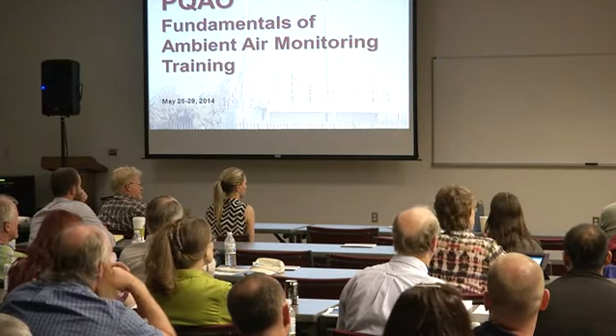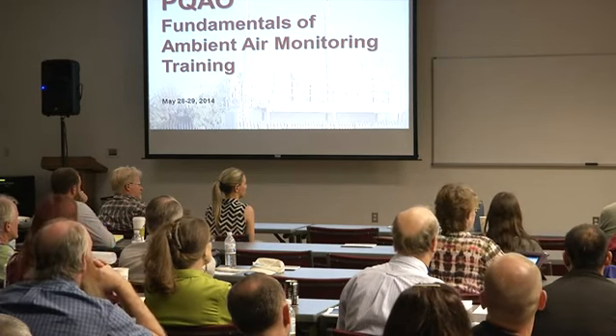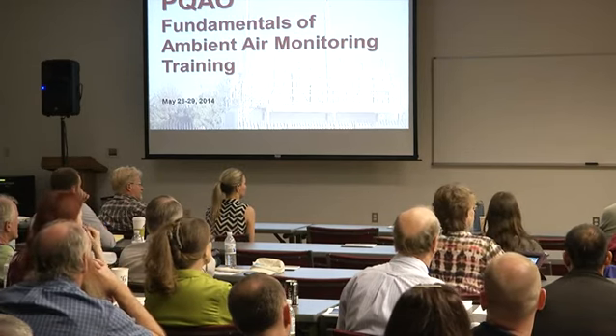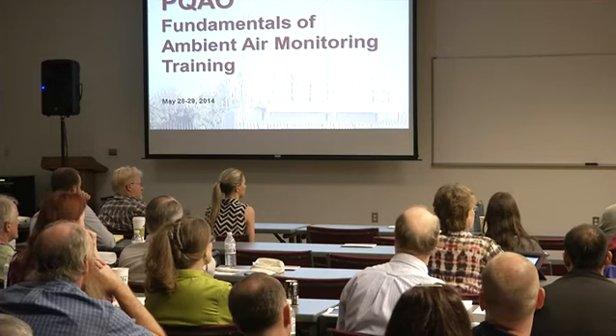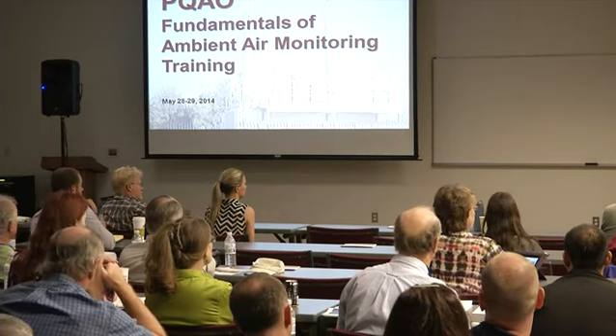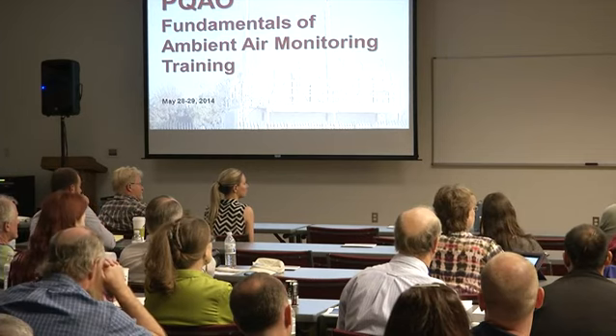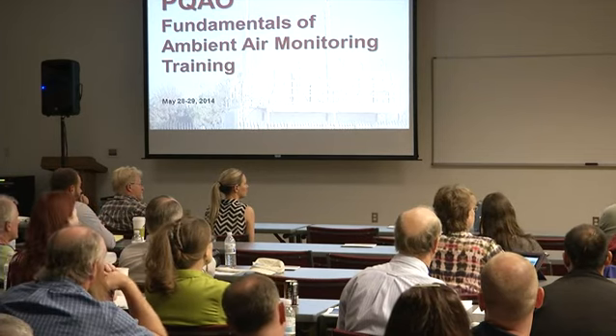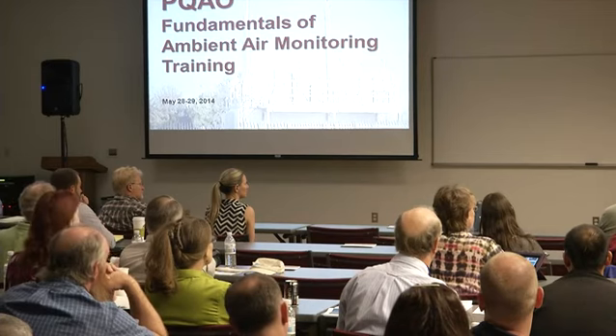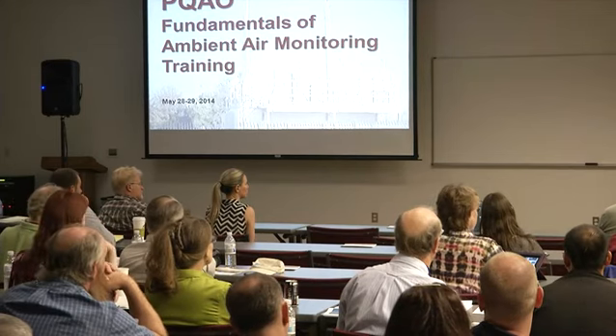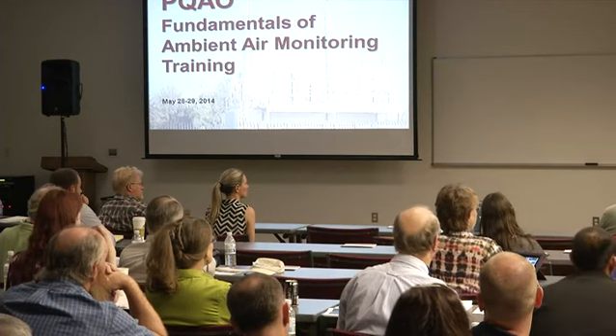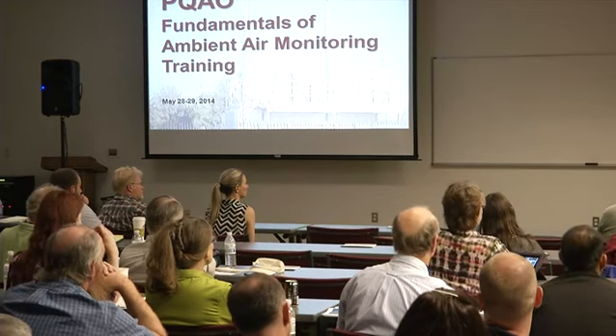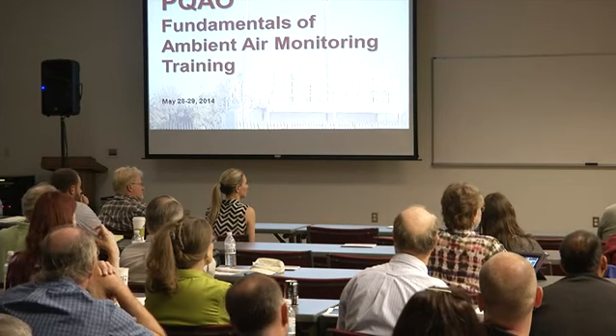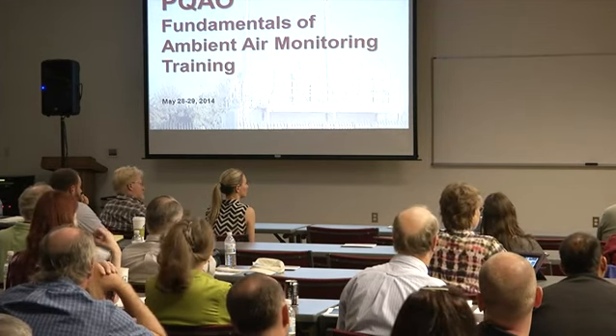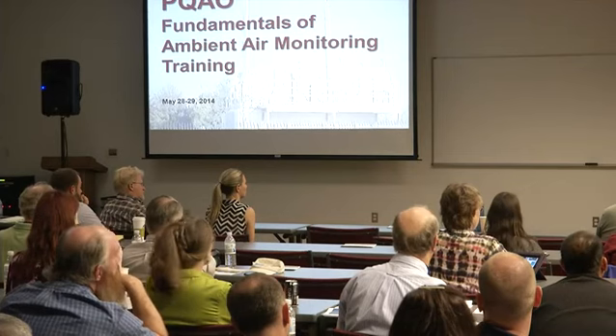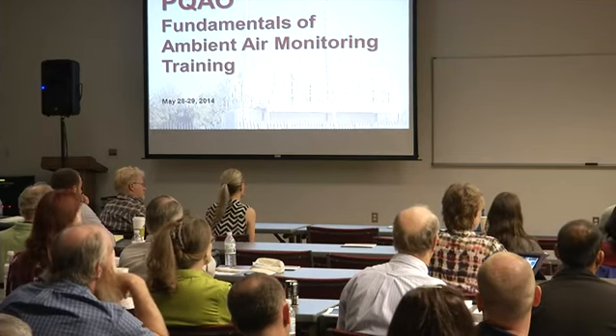There's a requirement that you keep the 24-hour standard deviation no greater than 2 degrees, per EPA regulation. But what we've seen with the BAMs in particular is that, from hour to hour, a swing greater than 2 degrees will have an impact on your concentrations. When measuring high concentrations it probably doesn't matter much, but at the low end, like with 2.5, that becomes critical. So you're trying to minimize that by keeping those temperature swings to a minimum.